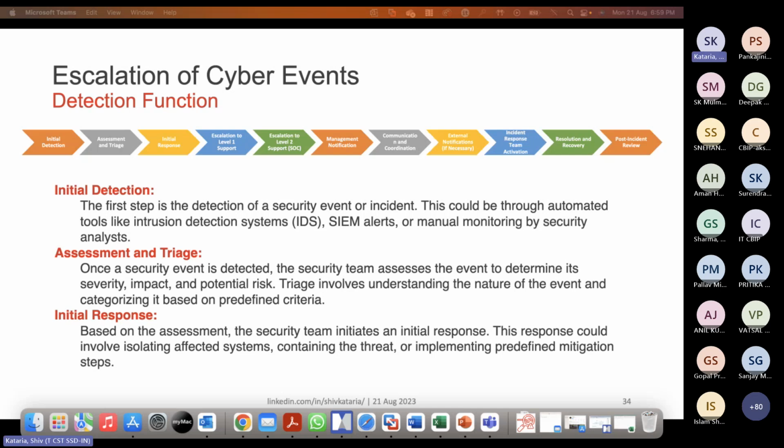I have seen recently, in one of the event analyses that we are doing, that an IT protocol packet had DNP3 written in the string. And since DNP3 was written in the string, the system alerted it as a malicious packet. So these kinds of things are basically false positives that do not require any specific action.